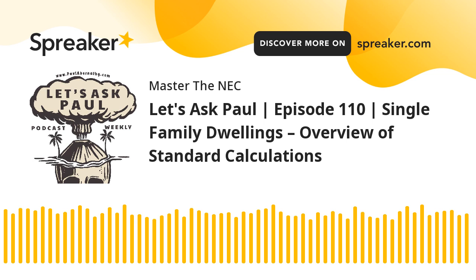So we've already taken the motors in this dwelling at 100%. Yes, we might have applied some demands to appliances, certain things that have motors. But for the most part, we've already done the 100%, right? What we haven't done is captured that 25% for the largest motor. So that's all we're really doing. Don't overthink this. I know people would like this to say this a little bit better, but that's what it's saying. You just kind of gotta go with me on this. Been teaching for 32 years. This isn't something new. So what you're trying to do is find the largest motor, and you're just going to multiply it by 25%. And then take that value, and that's what you add to your calculation.